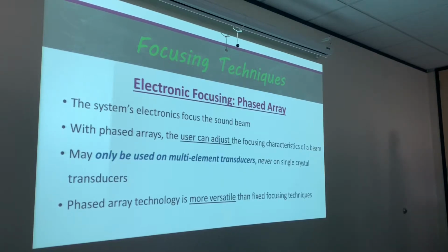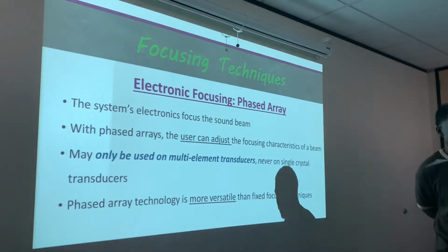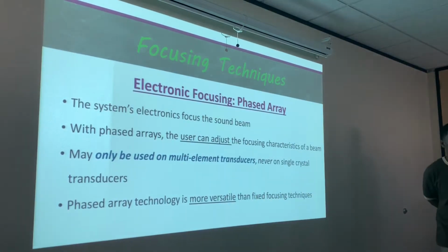So for the difference here, they insert the lens here, but here they just curve the active element. Absolutely. That's the exact difference. So with the acoustic lens, it's an extra piece inside of the transducer. With internal focusing, they're just curving the active element. They're changing the shape of it.